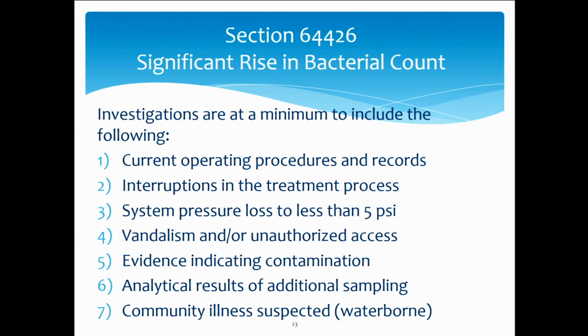The significant rise in bacterial count requires an investigation. There's some wordsmithing that has gone into it, but essentially the requirements are the same as in the existing TCR. You just have to look at your system operation, pressure losses, interruption of treatment, vandalism, evidence indicating contamination, analytical results, and if there's any community illness that's suspected.